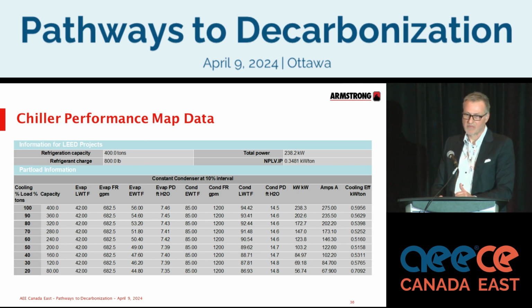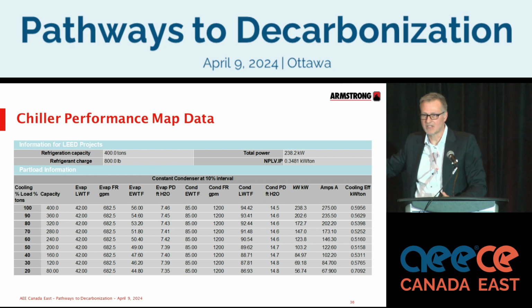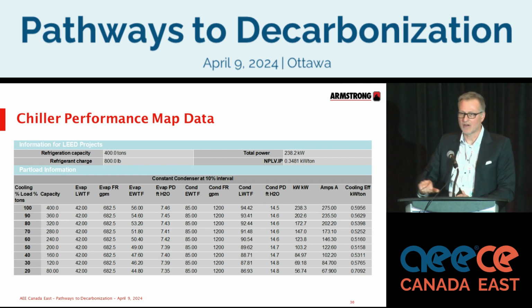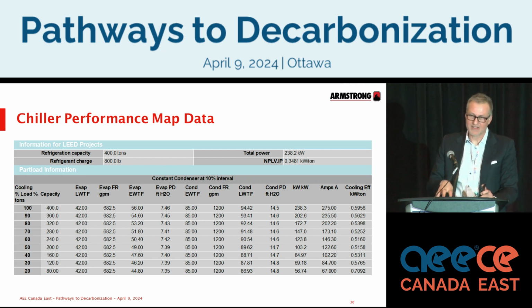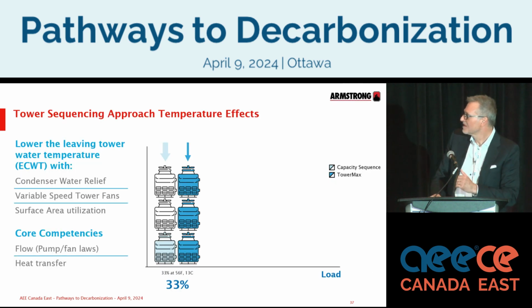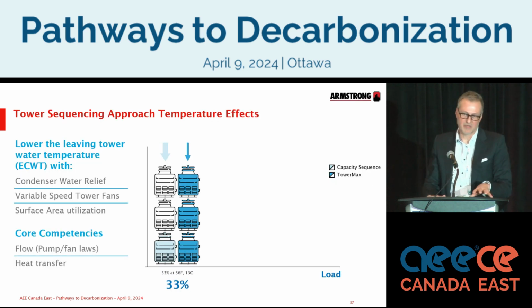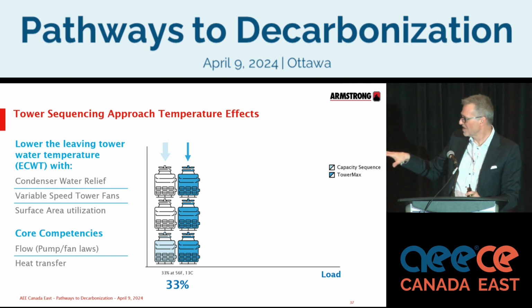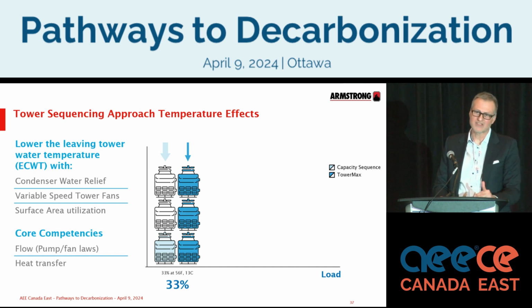10% savings. Now, the reason I bring this information up is that this is the data set, or this is the digitalization that's required for optimization. What happens is you take the data sets, you create digital models of your equipment. Once you have those digital models, you know how to stage that equipment based on load and demand. Secondly, then, on the tower side, and this is a big functional difference, typically the designs are 1 tower to 1 chiller. When you have 1 tower to 1 chiller, what that means is that you have to run that fan at 100%.